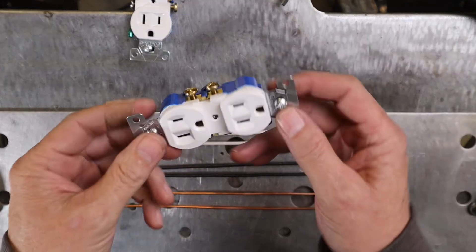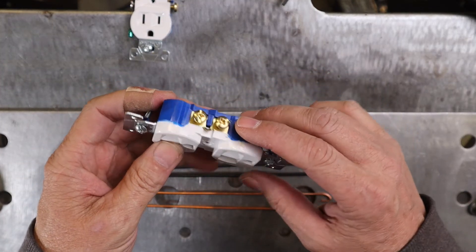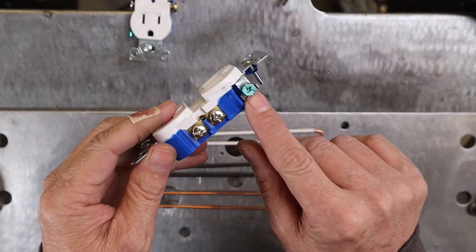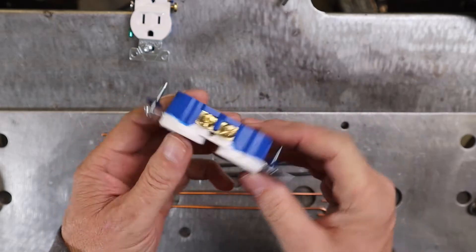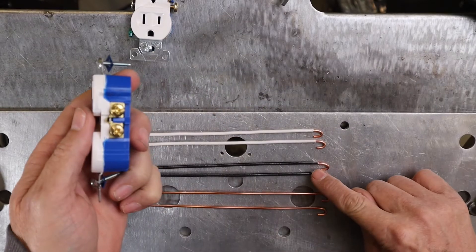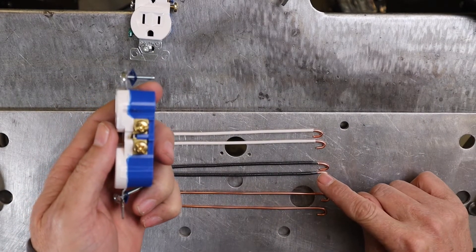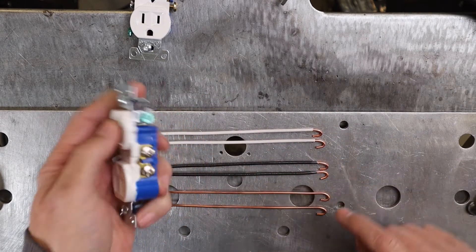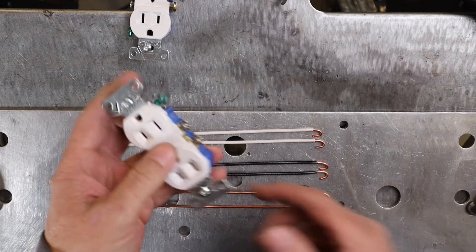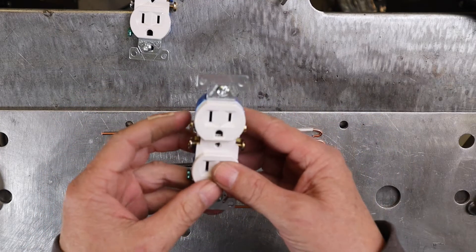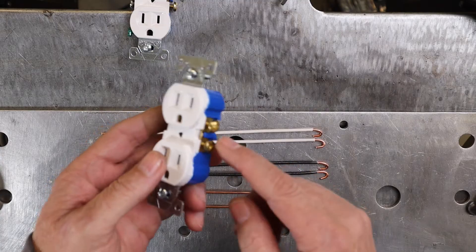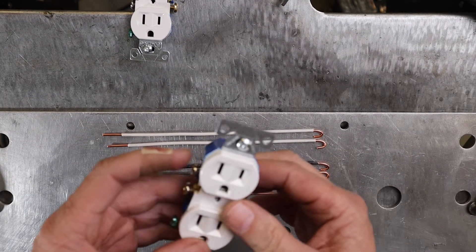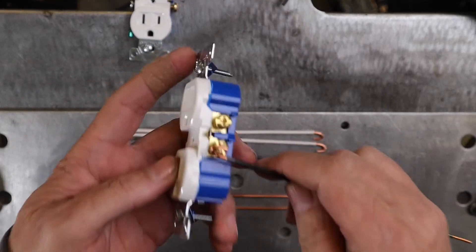The way these outlets work, you've got brass screws on one side and silver on the other, and then a green which is your ground. So brass is for black, which is the hot side. The silver is for the neutrals, the whites, and the green is the ground, which is the bare copper wire. So I'll just pick either top or bottom, it doesn't matter since they're both connected. I'll just go at the bottom, just make all mine the same.